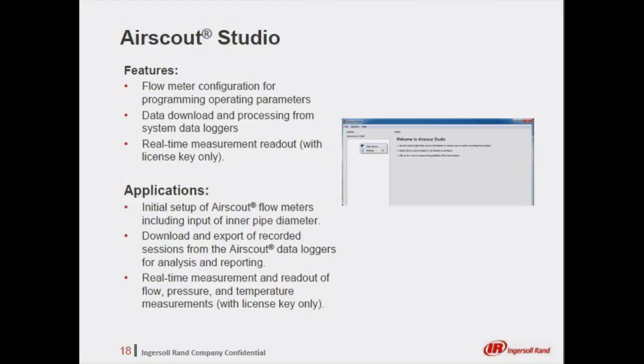The Airscout Studio is a configuration tool for setting up operating parameters. The Airscout Studio is capable of configuring any insertion probe with or without a display. The Airscout Studio also could be connected to the flow meters to download recorded data points for analysis. Real-time measurement readouts are available for all the flow meters with the purchase of a license key. And as I previously mentioned, the Airscout Inline with display and data logger, as well as the Airscout Terminal, have a micro USB to USB connectivity, and that's for connection into a computer and the Airscout Studio software. All the other flow meter probes will require an interface box to convert the RS-485 signal.